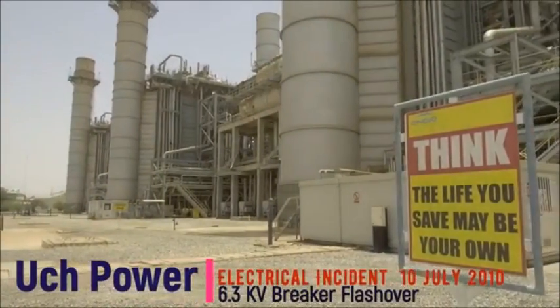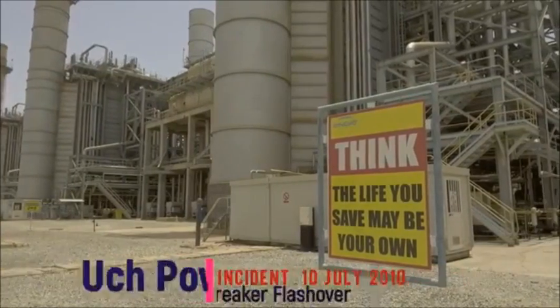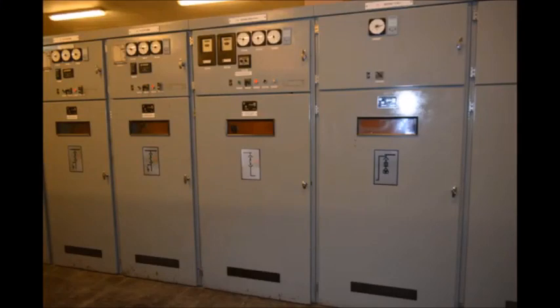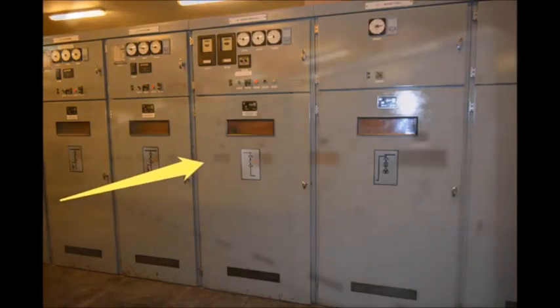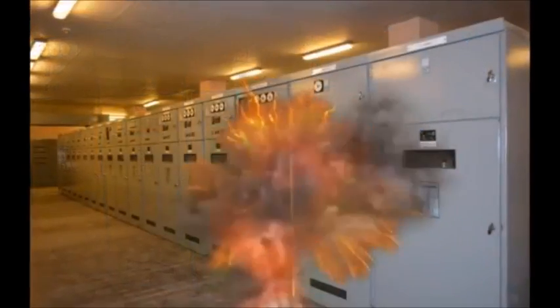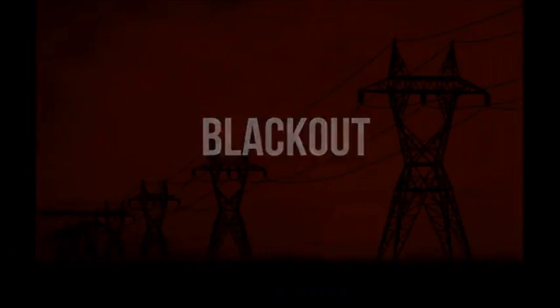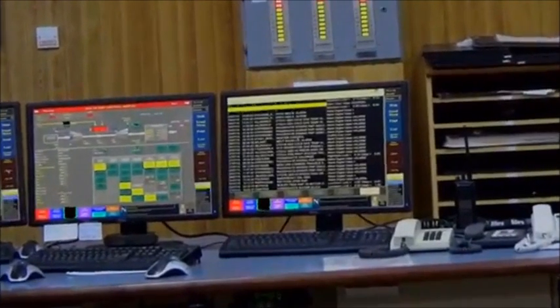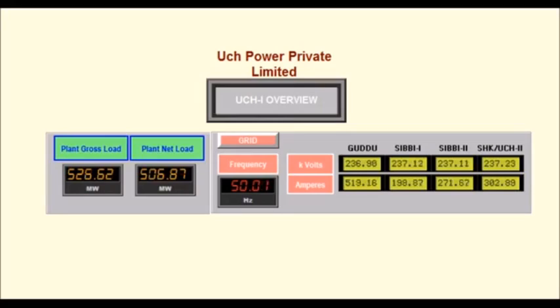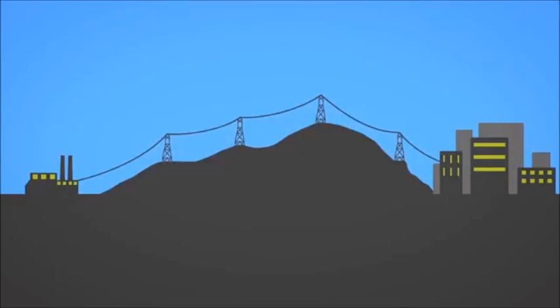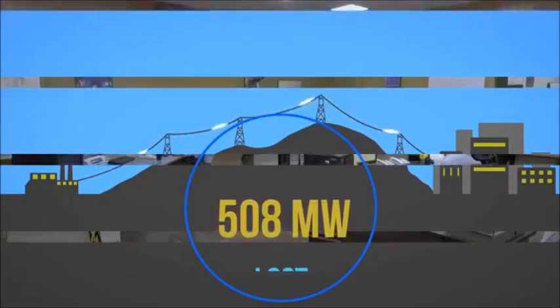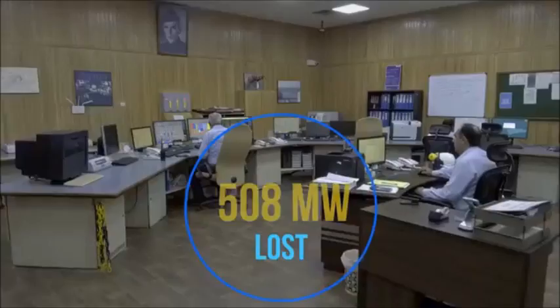Today we are sharing with you a significant event that happened at UCH Power Station when a 6.3 kV incomer breaker flashed over and caused a complete complex blackout. The breaker was in service at that time and no switching or other activities were in progress. The station complex was on base load with 508 MW sent out to the national grid.